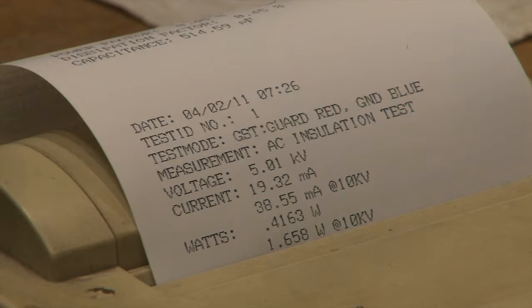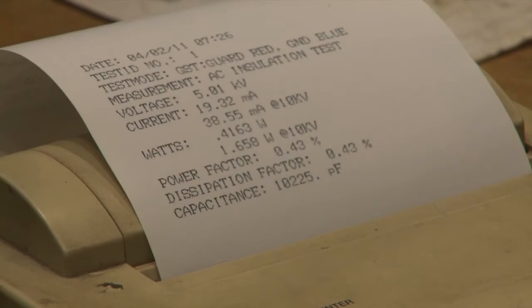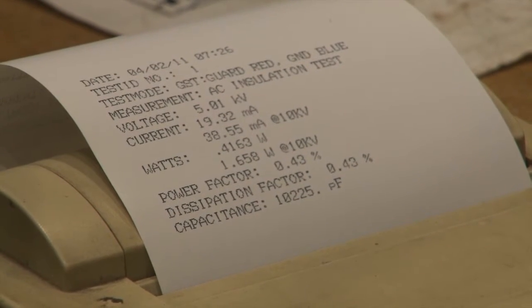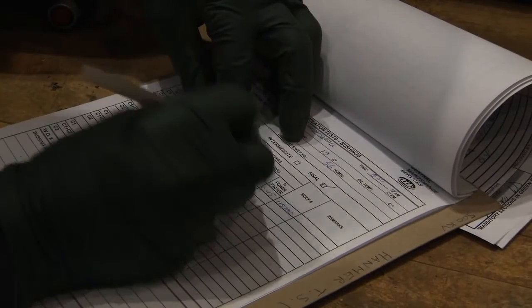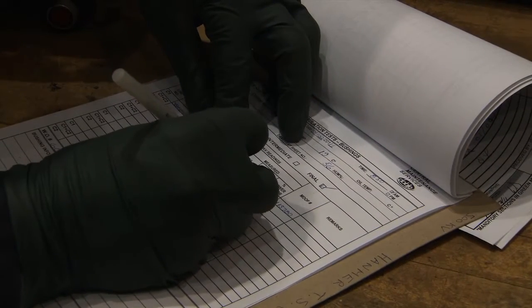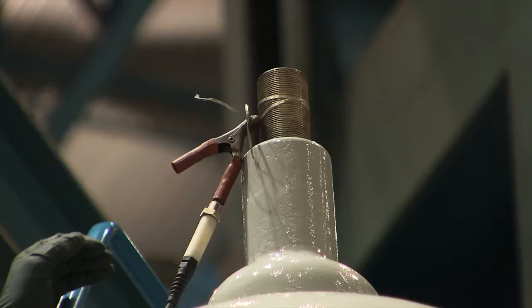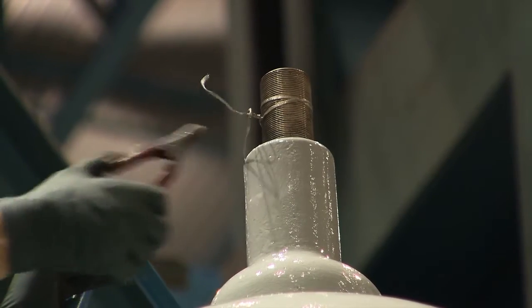When the test is complete, print a copy of the results and write the serial number of the bushing on the record. Record the temperature and humidity readings on the appropriate form. Disconnect the low voltage lead at the top of the bushing.